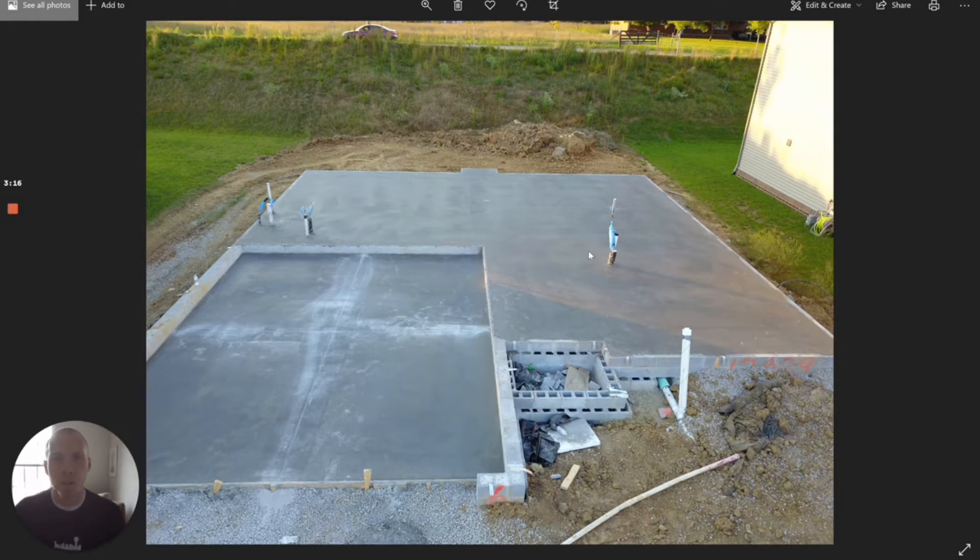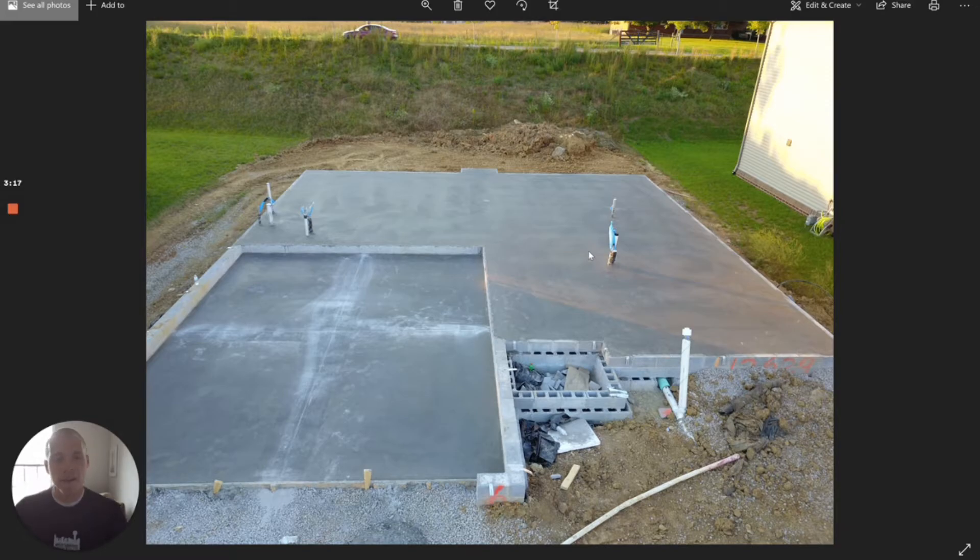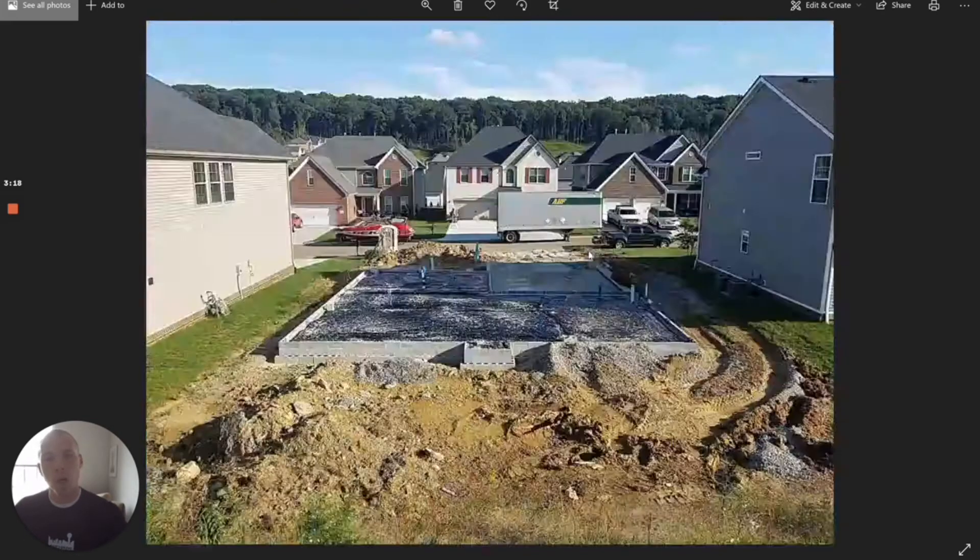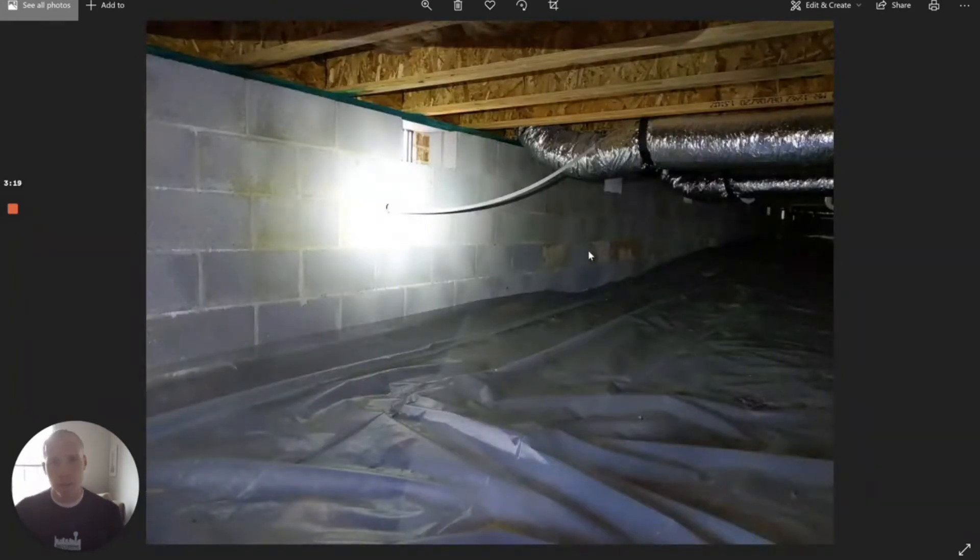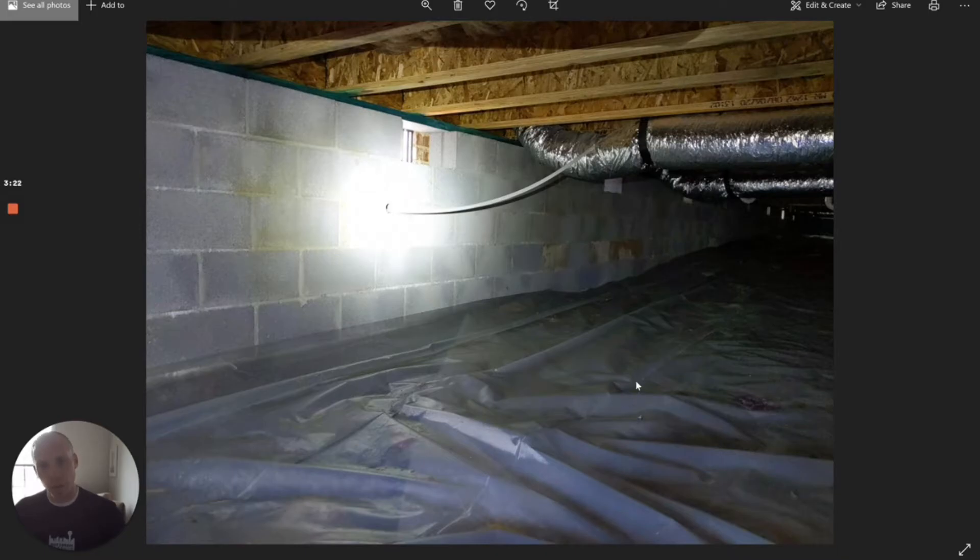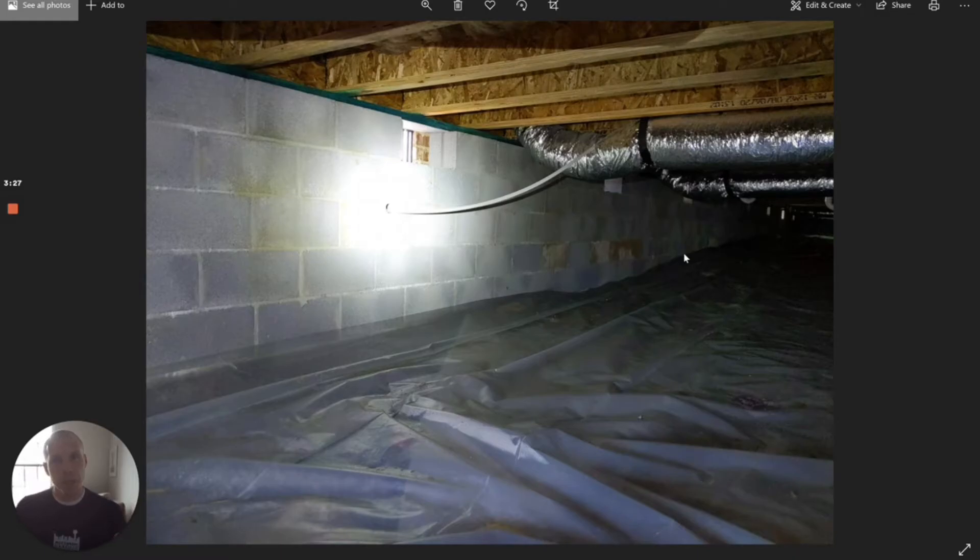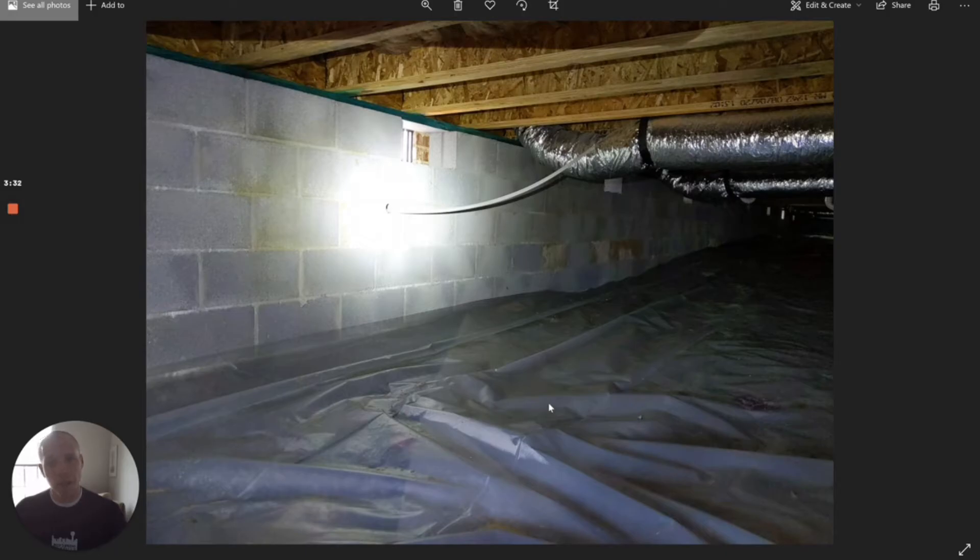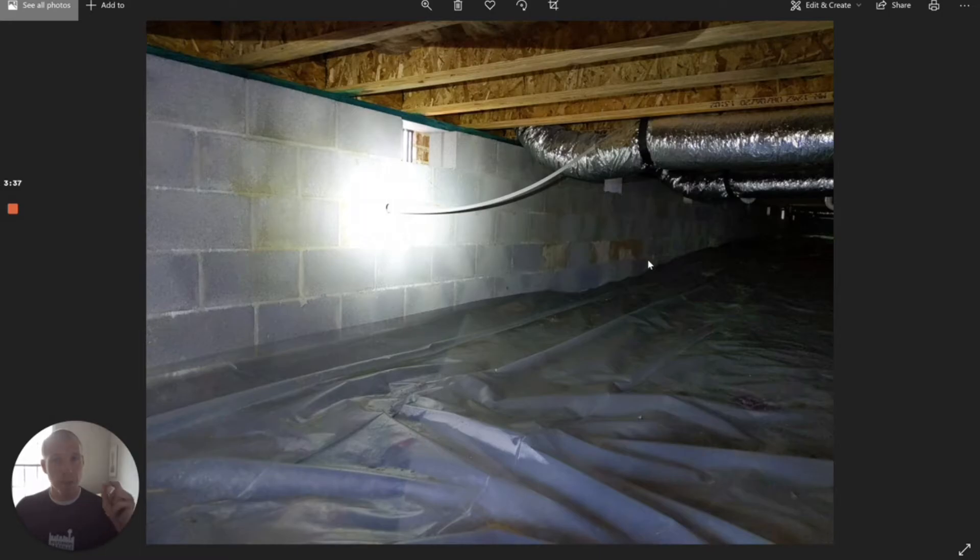Now if we go back to the crawl space situation, we've got loose plastic on the ground. Like I said, the edges aren't sealed off. If we have to put a mitigation system in here, what the EPA tells us that we have to do is we have to create a barrier between the soil and the crawl space. So that vapor barrier has to be thicker and it has to be sealed.